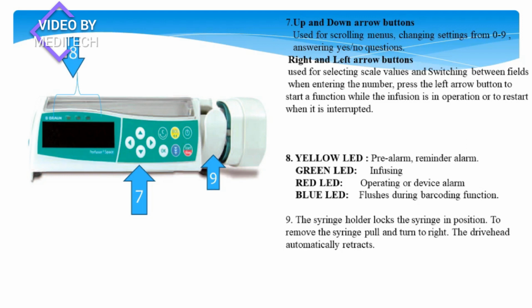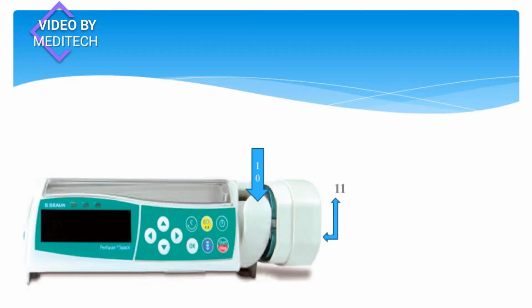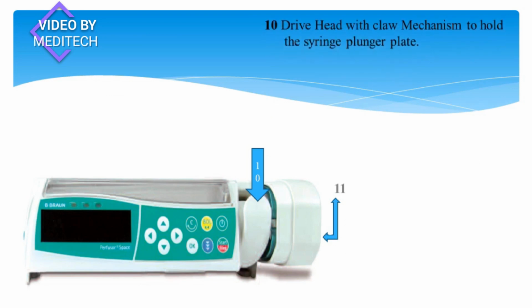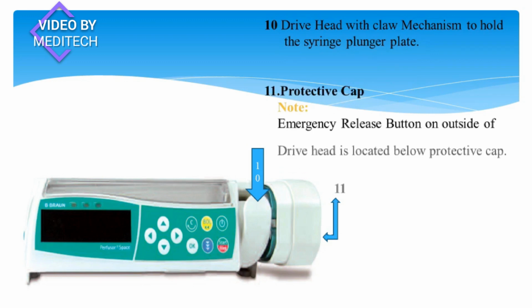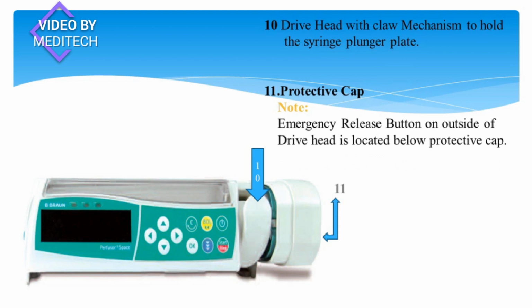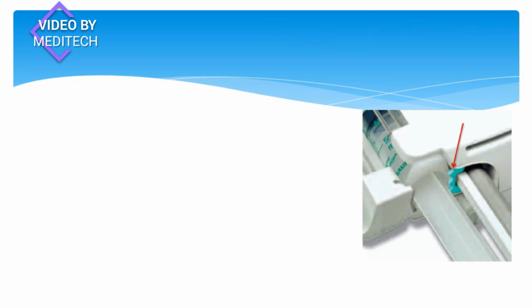And number 9, the syringe holder. Number 9 is the syringe holder, which locks the syringe in position. To remove the syringe, pull and turn to the right. The drive head automatically retracts. Number 10, drive head with claw mechanism to hold the syringe plunger plate. Number 11, protective cap. Note, the emergency release button on the outside of the drive head is located below the protective cap. Replace the protective cap after pressing.